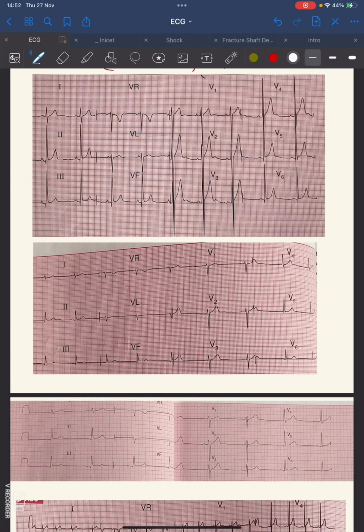Now, regarding ECG recording, the ECG is normally calibrated so that 1 millivolt of signal causes a deflection of 1 centimeter. Previously we have been saying that 1 centimeter equals 1 millivolt, which means 10 millimeters. This is the 1 centimeter, and this calibration is equal to 1 millivolt.